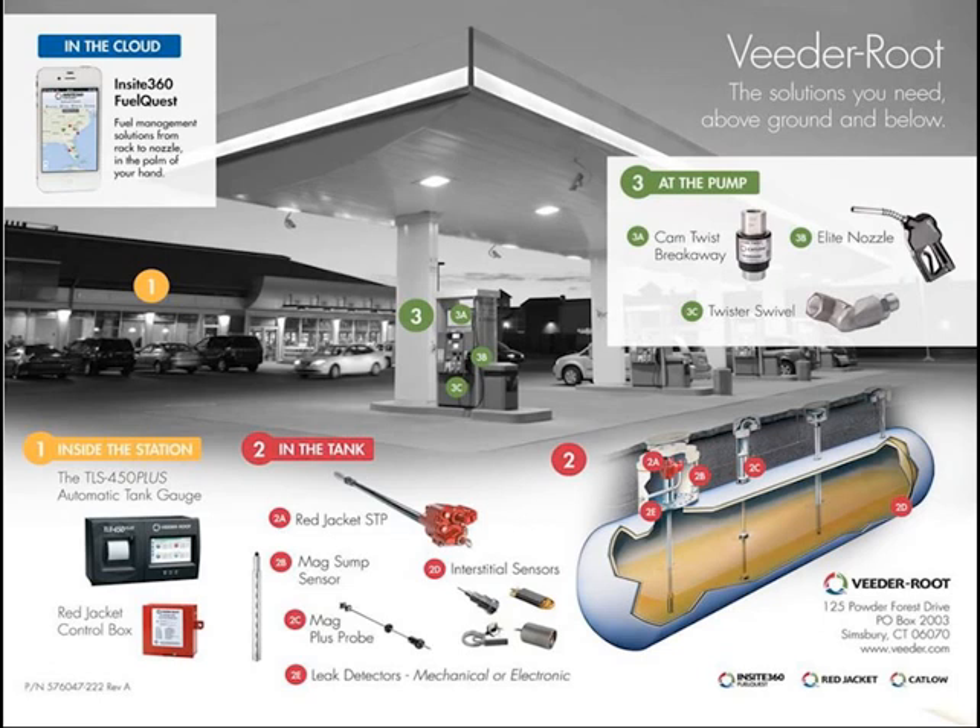Just to highlight Veeder-Root, Red Jacket, and CatLow equipment: we have extensive equipment in the field. We can monitor tanks for inventory, tank testing, and automatic reconciliation. We have submersible pumps to get product to dispensers, MAG probes for inventory and tank testing, and multiple sensors to monitor all containment areas. We also have the overfill protection device installed at the tank area that uses the in-tank probe to generate an alarm, and we use our cloud service Insite360 to give you all that data at your fingertips.